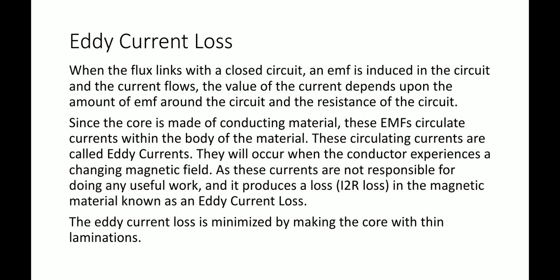When the conductor experiences a changing magnetic field, eddy currents are induced. These currents are not responsible for doing any useful work; instead they produce loss in the form of I²R heat in the magnetic material. This is known as eddy current loss. The eddy current loss is minimized by making the core with thin laminations.